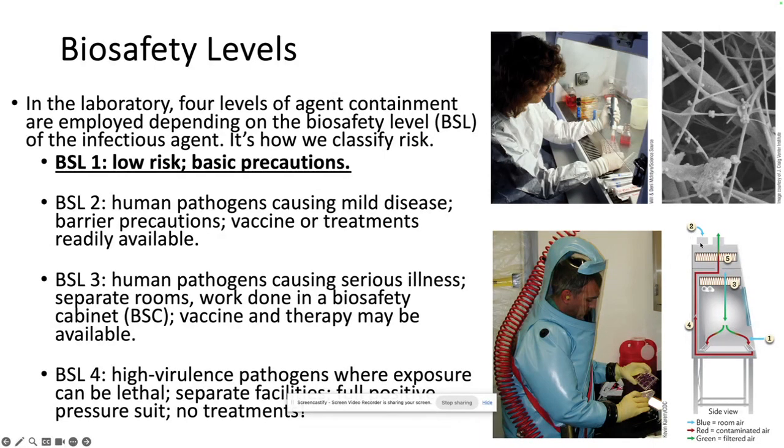Okay, so the air that comes in through the top is actually going to go through some HEPA filters. So it's going to be scrubbed and it's going to be filtered and clean when it comes into the biosafety cabinet. Okay, so you're going to do your work with your pathogen in this cabinet.